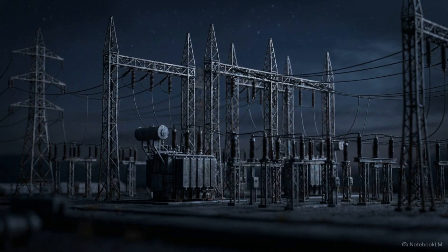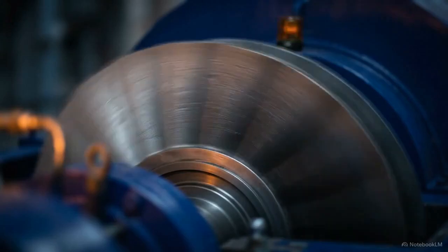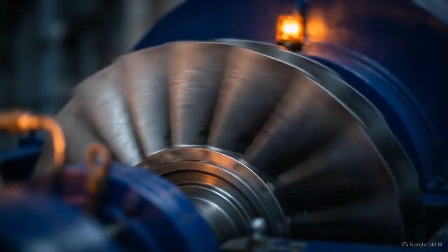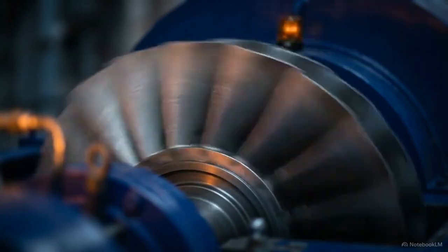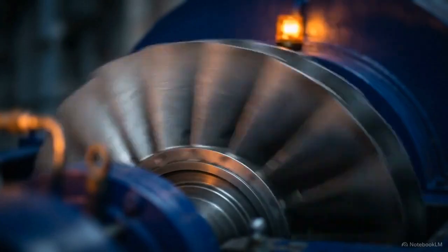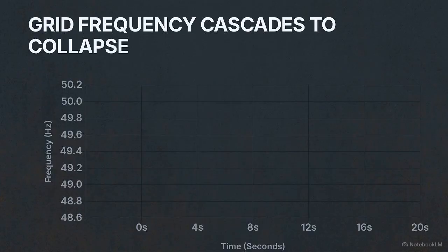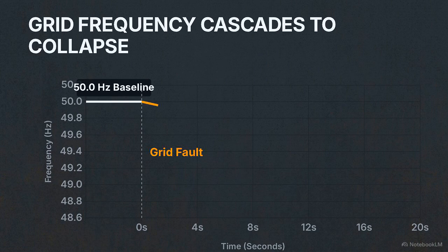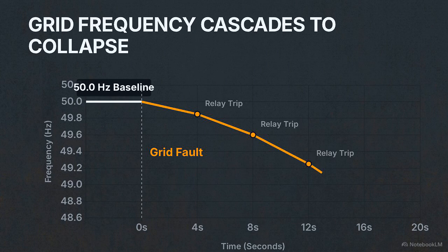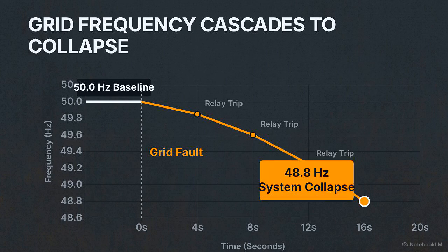A frequency drop is a physical threat to the hardware. As it falls, massive steel turbines and power plants begin to physically shake and vibrate. During a 2019 Great Britain event, frequency plummeted from a 50 Hz baseline to 48.8 Hz in 16 seconds. To save the turbines, automated relays disconnect generators from the dying grid. This drains more power, dropping the frequency faster and triggering a cascading feedback loop.